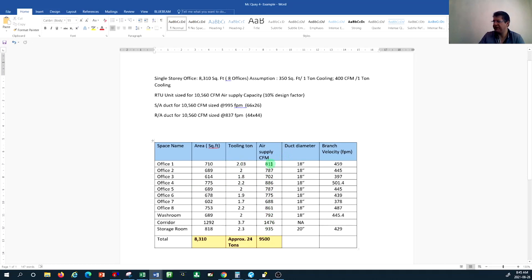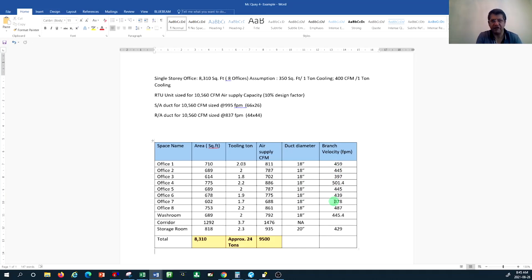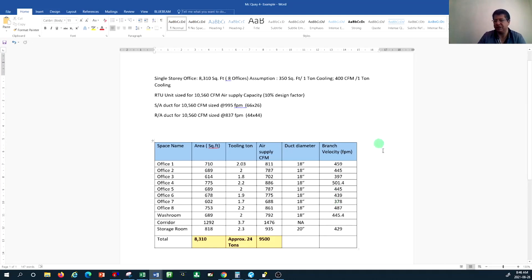We determined the air supply rate and I sized the duct work for offices for different branches — 18 inch round diameter — and the branch velocity is below 500 feet per minute for most of them, which creates much lower noise in the space. It's a combination of factors: velocity, noise level, and material usage — you don't want to oversize your duct work so much that too much material is used to construct it.